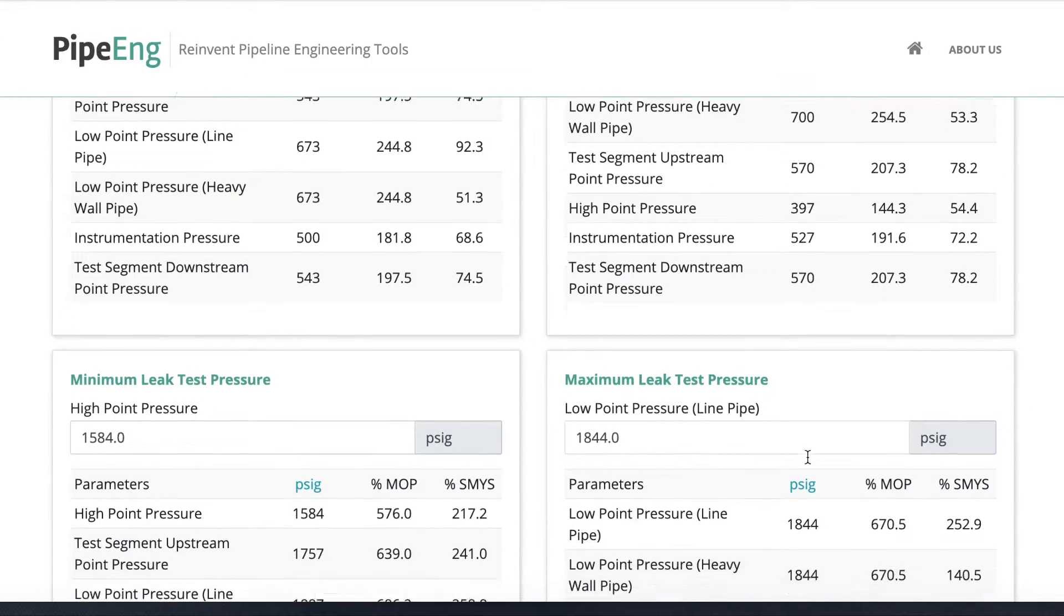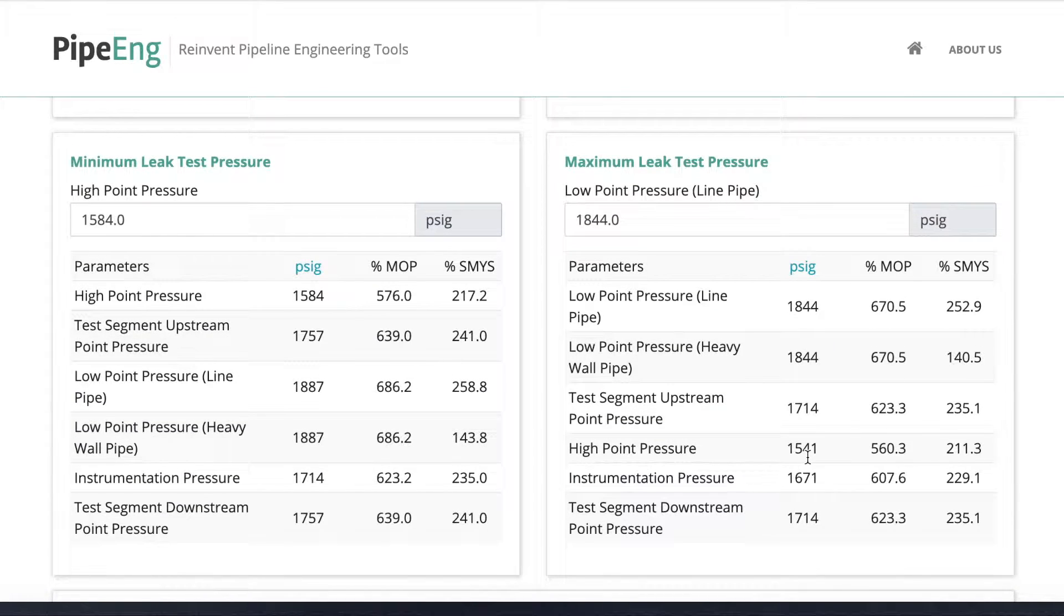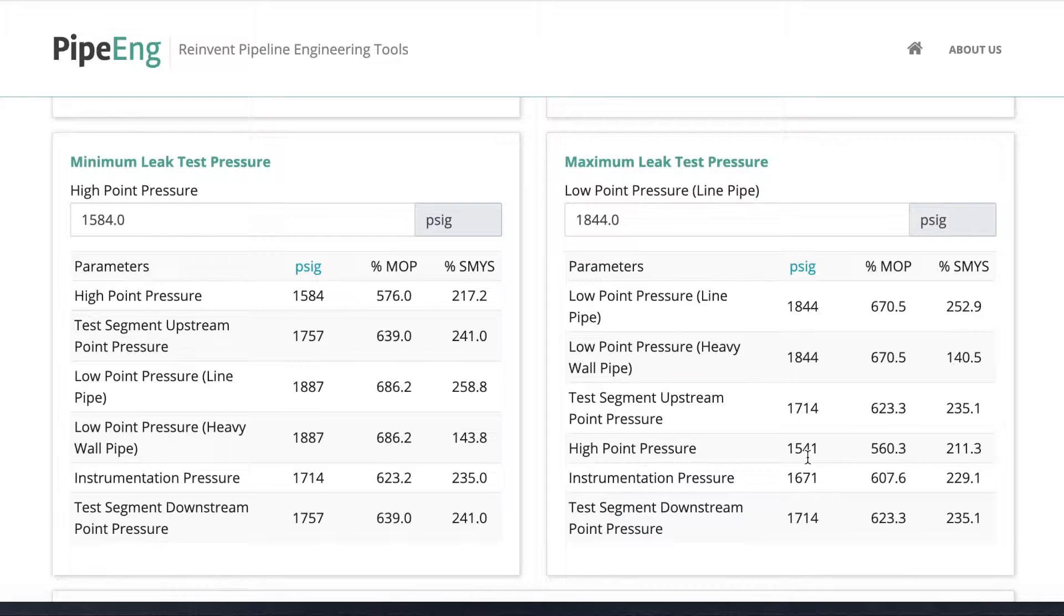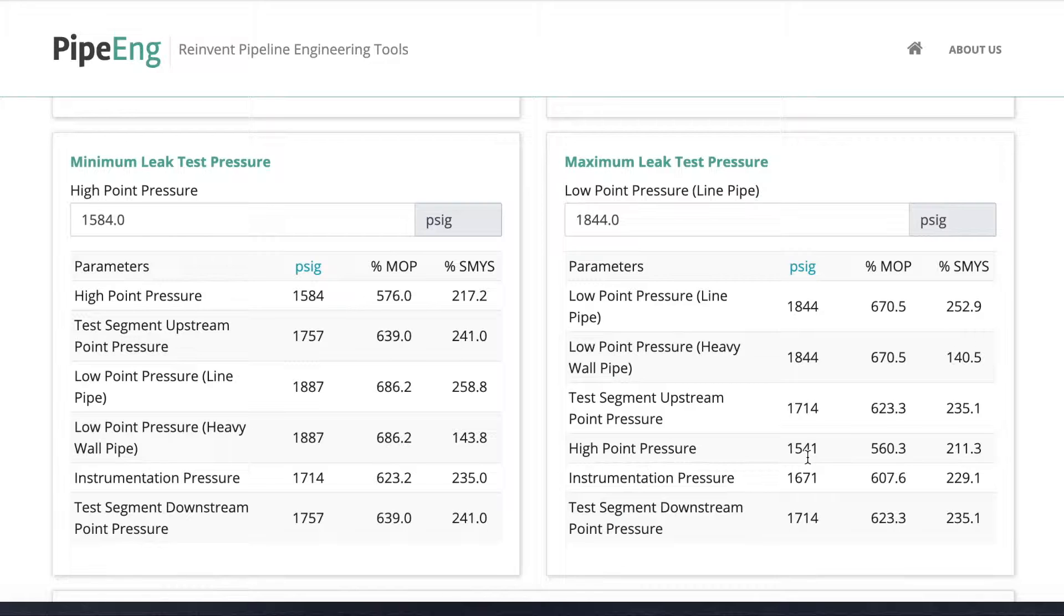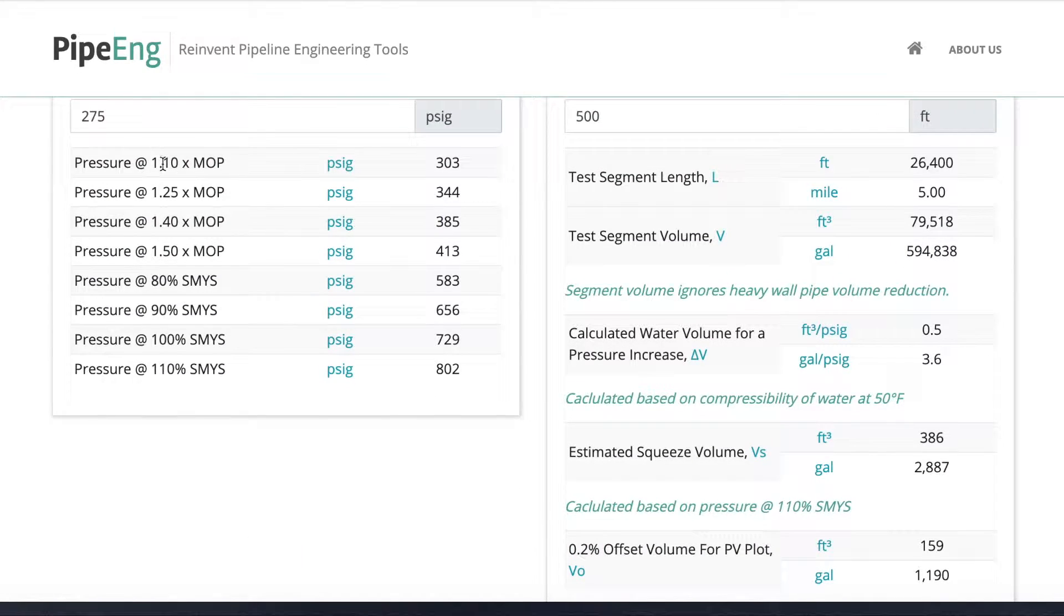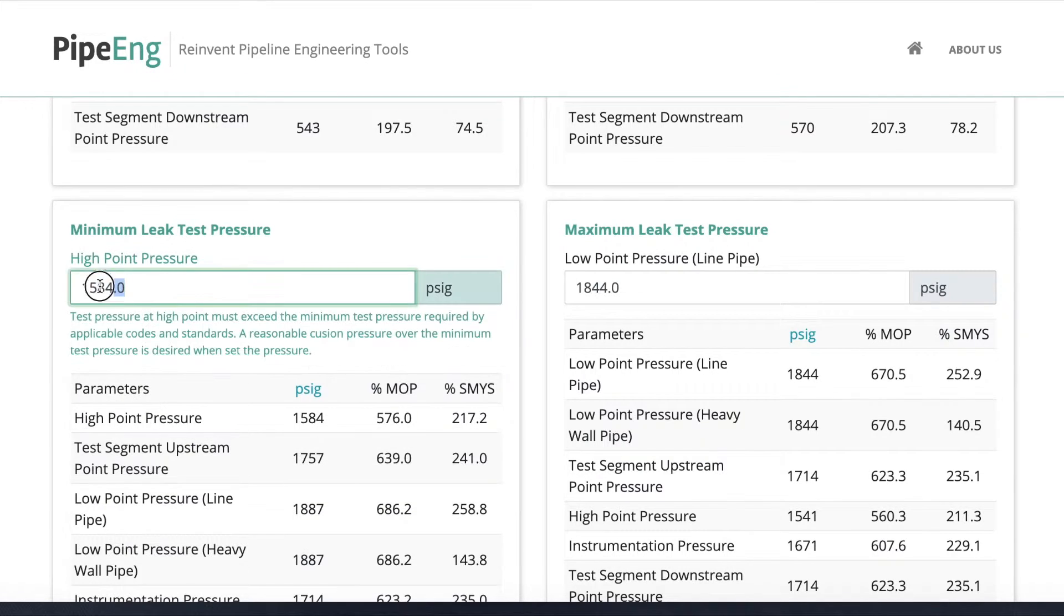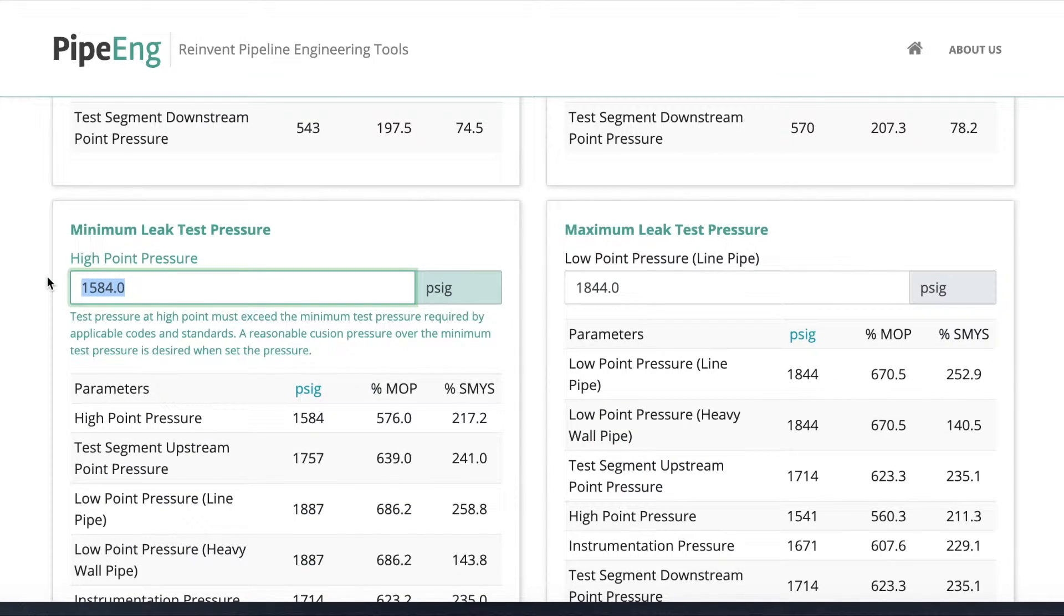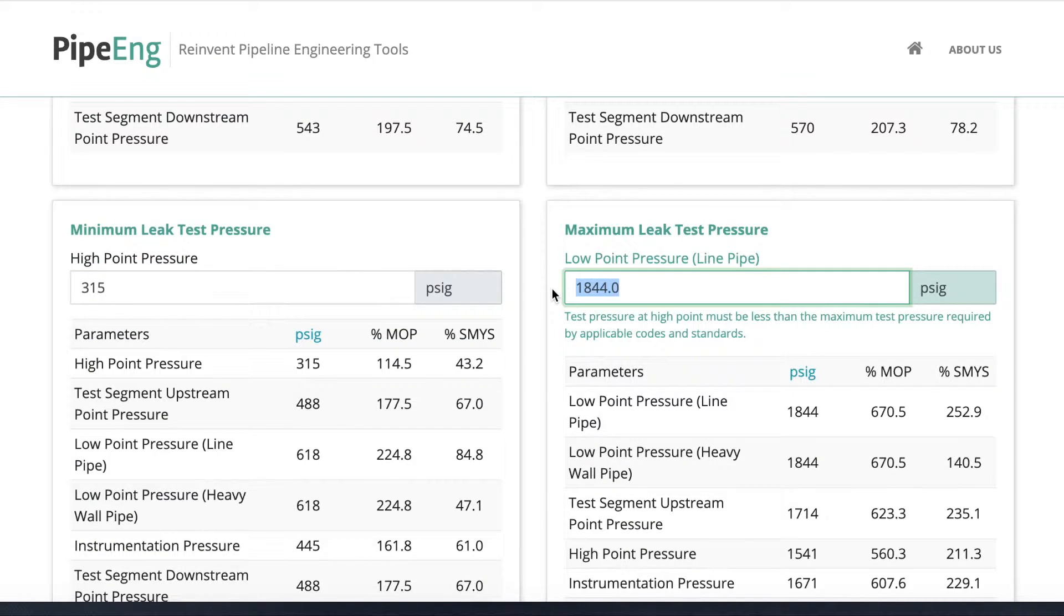Similarly, if we require a separate leak test, it depends on which code you comply with. Usually, we will do a leak test followed by a stress test. The leak test usually happens at a lower pressure. So in this case, let's assume we have a leak test with a minimal test pressure of 110 percent MOP, and the maximum test pressure for leak test is still 100 percent SMYS. So in this case, we go back up and we find 110 percent MOP is 303. So here I want to put the high point during the leak test is 315 PSI. And for the maximum pressure, it's going to be the same as the strength test is 700 PSI.